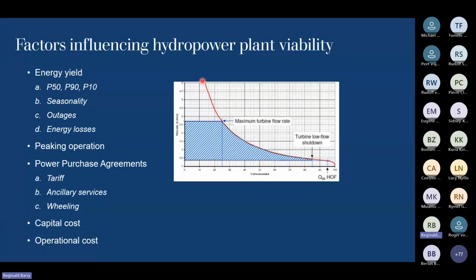So we look at this and decide to size the turbine typically for 25% up to 70, 80, 90 percent - in this case, say 85% exceedance - and use the flow data points along here to calculate the energy yield. From this you calculate your P50, or 50% exceedance probability, 90% exceedance probability, and 10%, and use that in your financial model to stress test it - to see if you hit a dry year, can you still make this scheme financially viable.